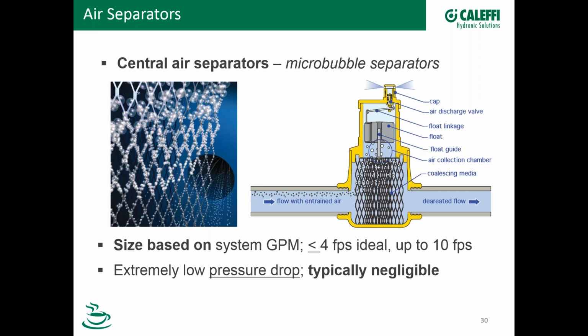Now, I mentioned low pressure drop. Typically, that's a negligible thing. So when you're doing your head loss calculations in your piping, you don't need to count these. You don't need to count an air separator. If you want to, you can look in the literature that we offer. There is a flow versus pressure loss graph in our literature, but it's a really, really small number. So check that out if you want to. But again, typically we say you don't have to worry about it.